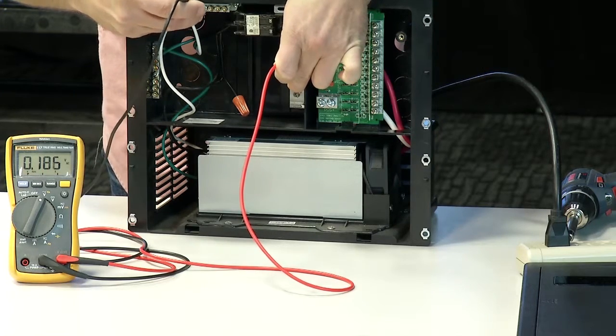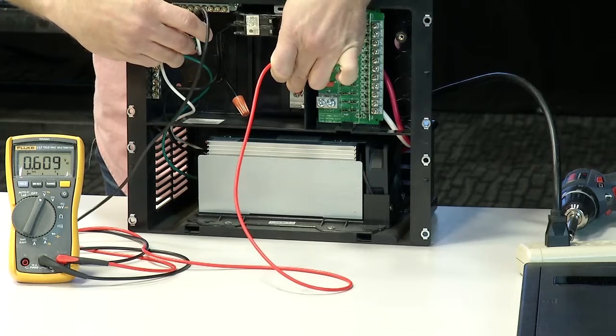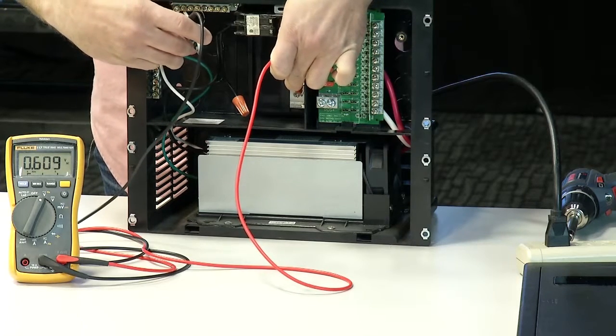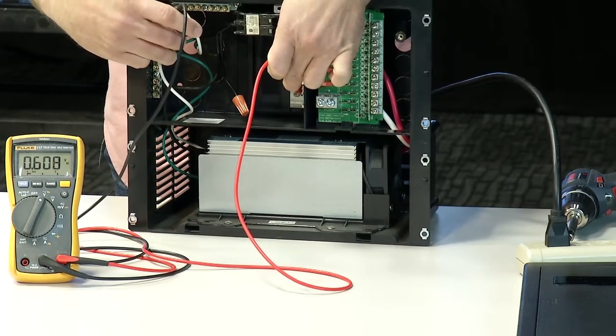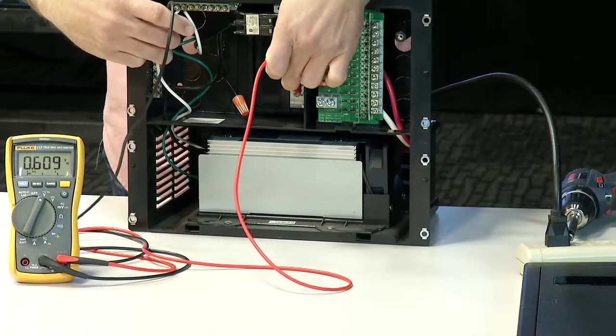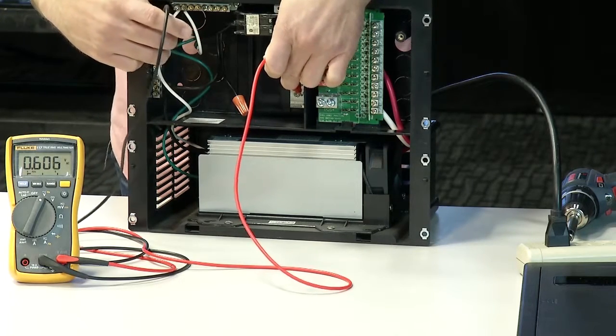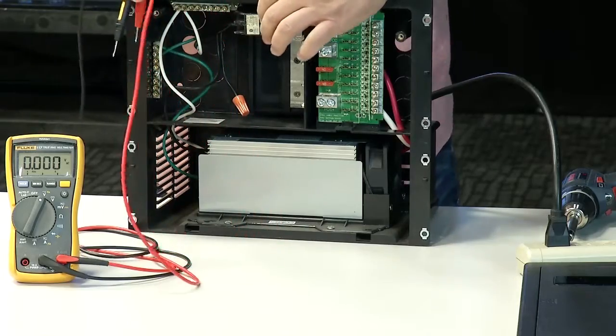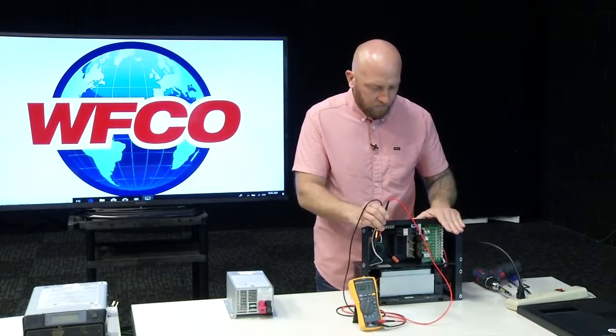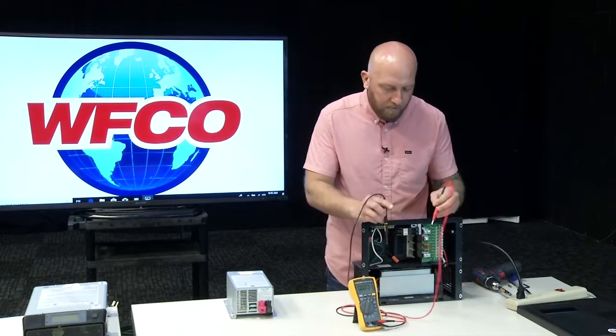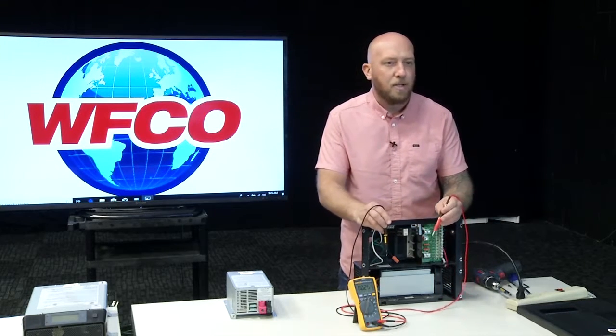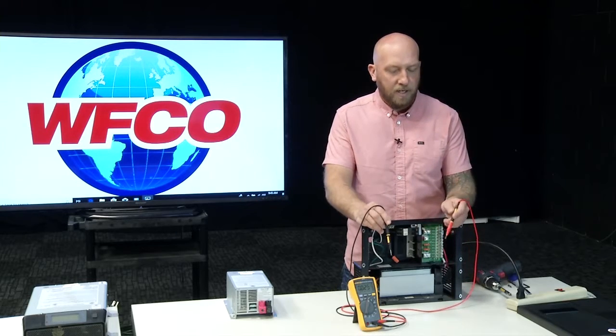I'm going to check from neutral to ground. Also nothing. So we know we have power coming in, and my breaker's off, and my breaker's working properly. So I'm going to go ahead and flip our breaker on. I'm not sure if you could hear that, but the fan has actually spun up for about 2 seconds. That's normal, and it turns right back off.